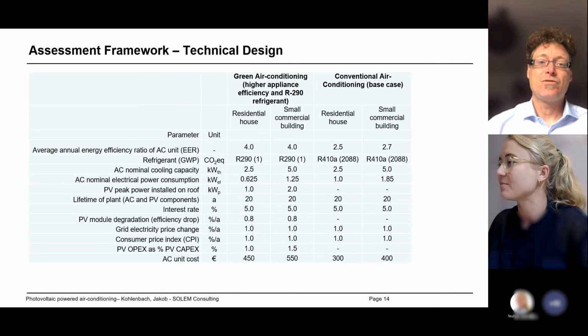That is our base case. The difference being the refrigerant used and the energy efficiency ratio of the air conditioning unit. The green air conditioning units, using propane as a refrigerant, R290, have an energy efficiency ratio on average over the year of 4. For those not familiar with that parameter, it basically says that 1 kilowatt hour of electrical energy will give you 4 kilowatt hours of cold or heat removed from your building. The conventional air conditioning uses R410A with an EER of 2.5 or 2.7 respectively.